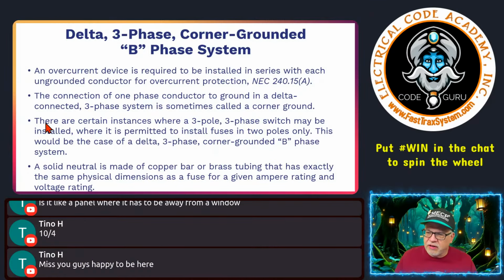It says there are certain instances where a three-pole, three-phase switch may be installed where it is permitted to install fuses in two poles only. This would be the case for a delta three-phase corner-grounded B-phase system. This is a case where one of the phases is intentionally grounded, and there are specific types of applications where the code would permit you to have fuses in only two of the phases, and the third phase is actually a grounded conductor. Rare, but you might run into that situation out in the field.